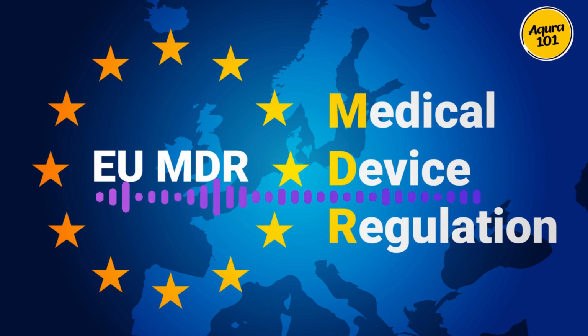Absolutely. The MDR takes a cautious approach. First and foremost, reprocessing can only happen if it's specifically allowed by the national law of the EU country where the reprocessing is taking place, so it's not a blanket EU-wide permission. Each country gets to decide its own stance on this based on its own assessments of the risks and benefits. Exactly. And even if reprocessing is allowed, there are stringent requirements. Okay. The MDR considers anyone who reprocesses a single-use device to be the manufacturer of that reprocessed device. So they're essentially taking on the responsibility of the original manufacturer. Exactly. They become fully responsible for meeting all the requirements of the MDR, just as if they had designed and manufactured the device from scratch.